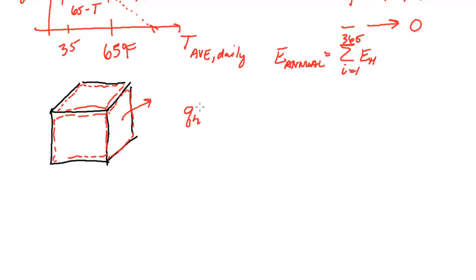And how much heat is lost through the building, through the building surface? We're going to call that QH. This is heat loss and this would be a unit of energy per time or BTU per hour. Well, that rate of heat loss is going to be related to, one, the size of your building. So how much surface area you have. If you have more surface area, you're going to have more heat loss. It's also going to depend on what materials that wall is made out of. Is it made out of, do we have a lot of insulation, is it made out of concrete, is it made out of wood? This U value takes all of that into account. And then lastly, we need to know, well, the rate at which it leaves is going to be related to how cold it is outside. And we're going to assume that we aren't going to need any heating unless it's less than 65 degrees.